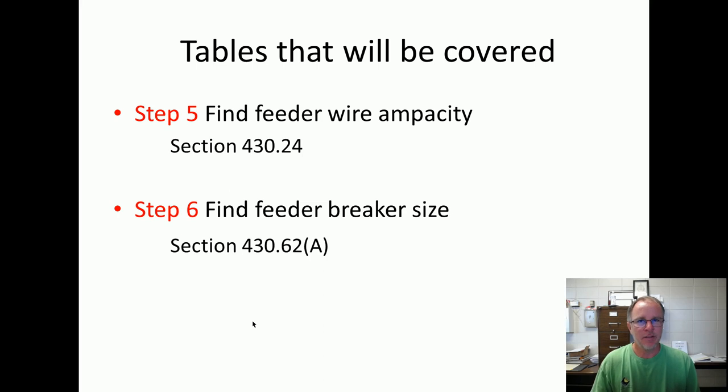Steps 5 and 6 are for multiple motors. Let's say you've got a feeder wire and you're tapped onto that feeder wire and you ran 3 motors off of it. It's kind of like the bus duct in my shop. We pull on the table, we'll pull 3 or 4 motors down. Well, the feeder is supplying each branch circuit's motor wire, so we've got to upsize it.